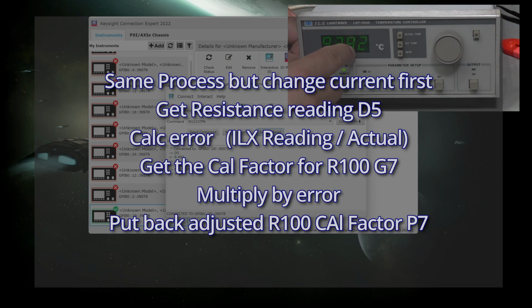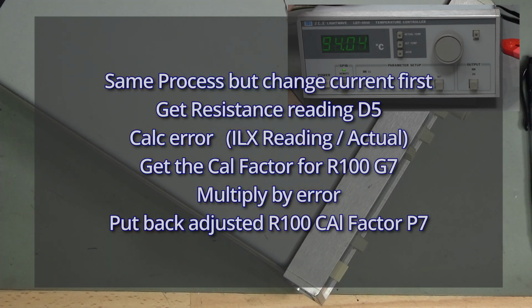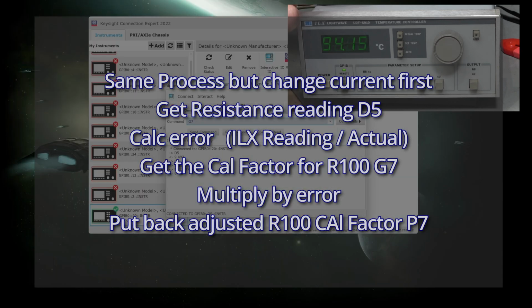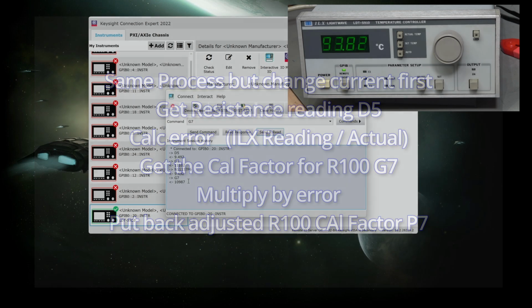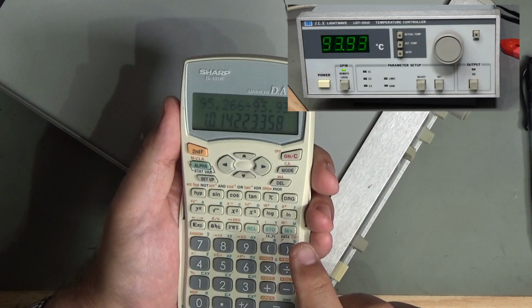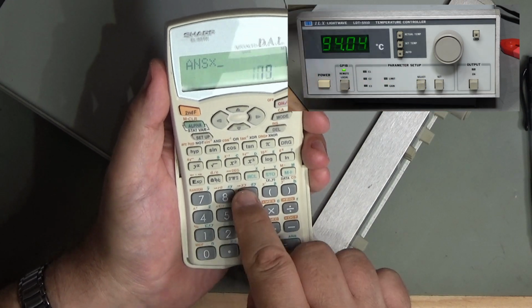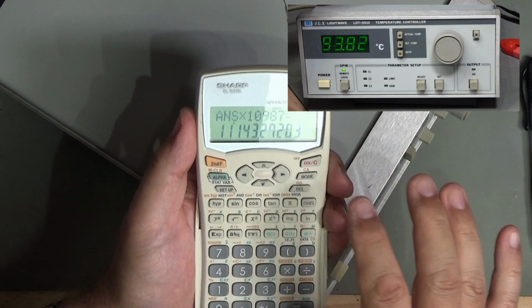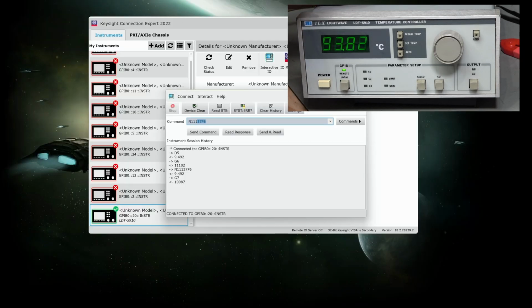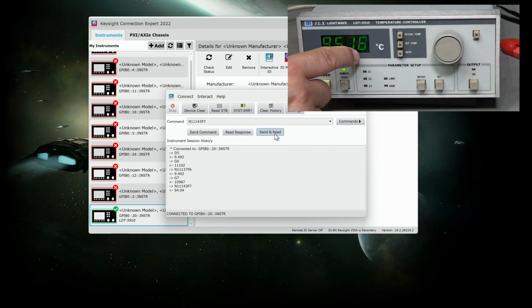So I'm going to go for 93.93 because that seems to be roundabout in the center. So in the same way, I'm about 1% off. So just like I did before, G7 this time because I need to get the right value. And there is my adjustment factor, 109 blah blah blah. So I multiply by the error, 10987. That gives me 11143. And N11143P7. And send and receive. And now if we look on the screen, we're going 95.16, 95.38, and we're kind of in the middle of that range. 95.266 is the actual value of the resistor we've got connected, but we are picking up a bit of noise.